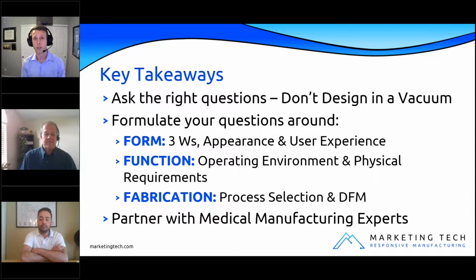We group those into three F categories: the form, function, and fabrication of the device. So with form, who's going to be using it, what's the primary use, and where is it going to be used? That's the starting point. And that's going to dictate the look of the device, the footprint of the device, and how the user experiences using your device, which is such an important component.